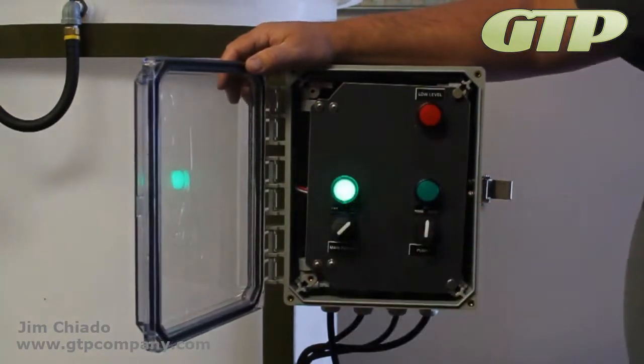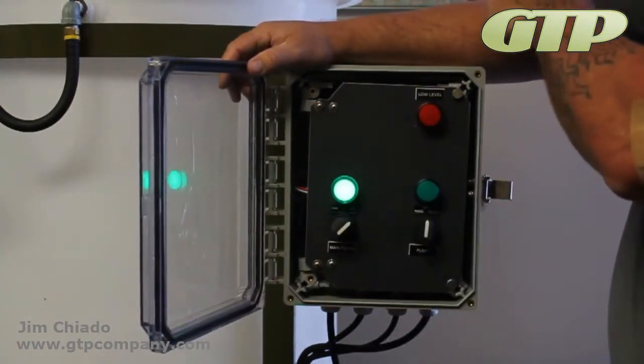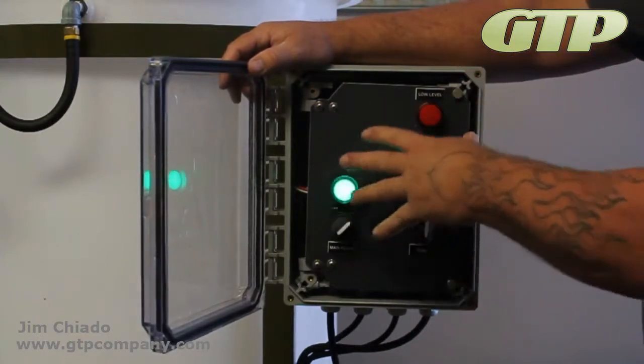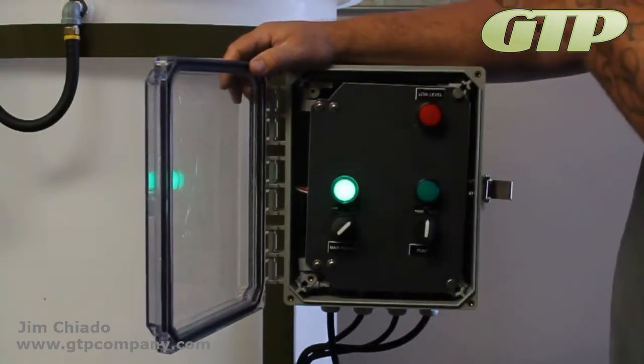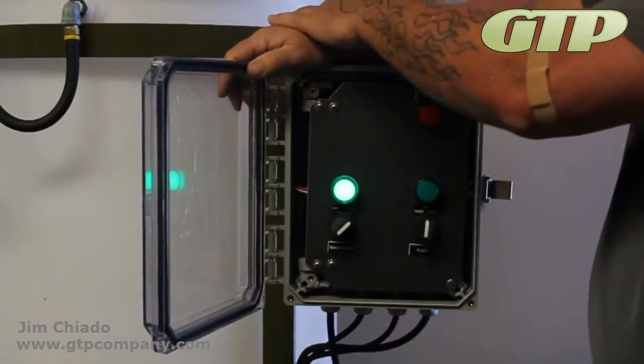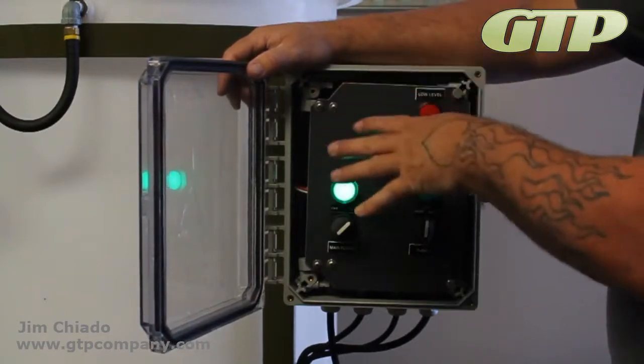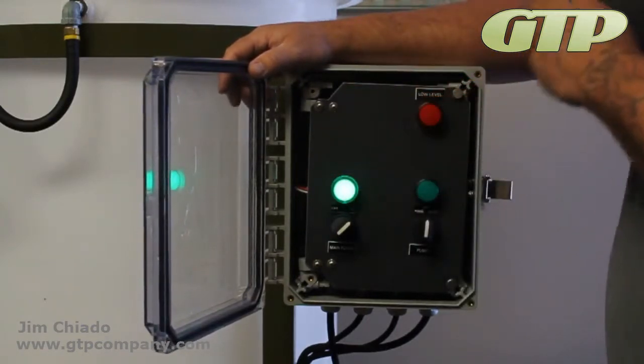Main power switch. You can see it does flash low level really quickly because it's getting a low level signal before it goes ahead and says go ahead and power up. The reason it does that really quickly is because if something fails with that low level, it will fail low level. If it breaks or whatever, we've wired it as a safety feature.